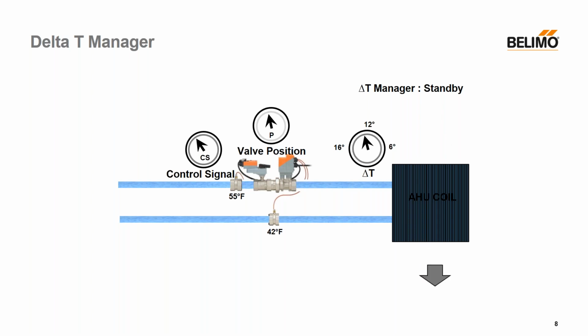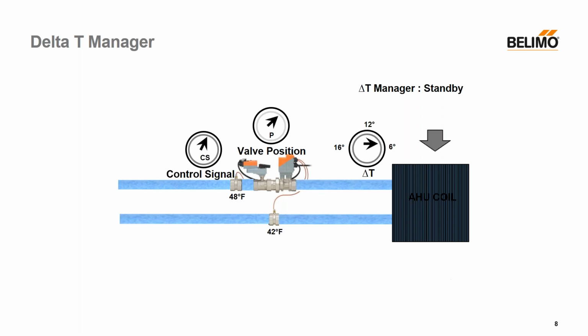As my system starts to overflow, as our control signal opens up, something different will happen. If we watch our dials now, as we click, our control signal is increasing, our valve position is opening, and our delta T has dropped. We were before at around 13 degrees, and in this example, we've dropped to 6. These numbers are relative to the case study that we're going to talk about in a second. We're not getting that good heat exchange out of our system. Essentially, we're not using the water. The water passes through the coil too fast. We can't get that efficient heat transfer out of it.